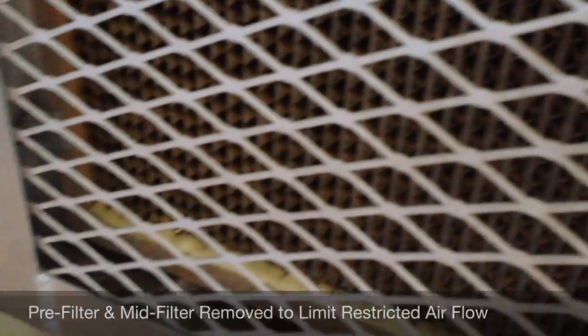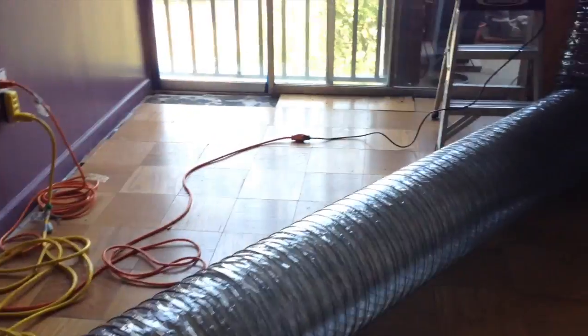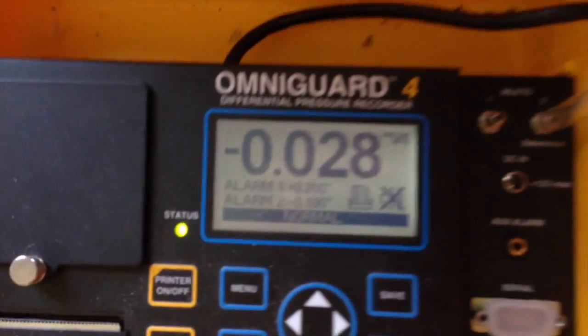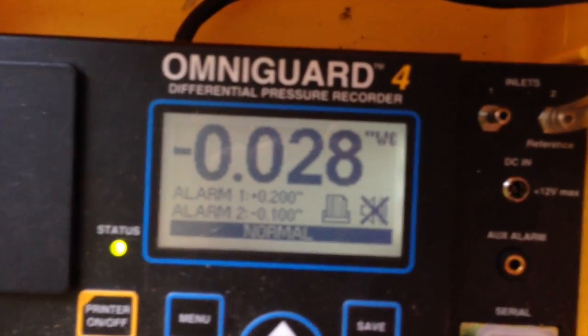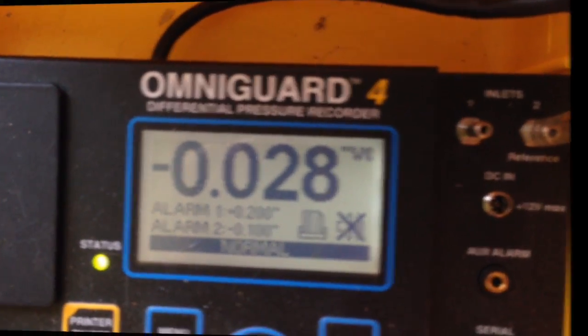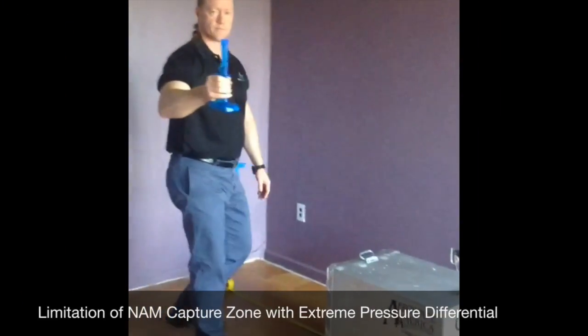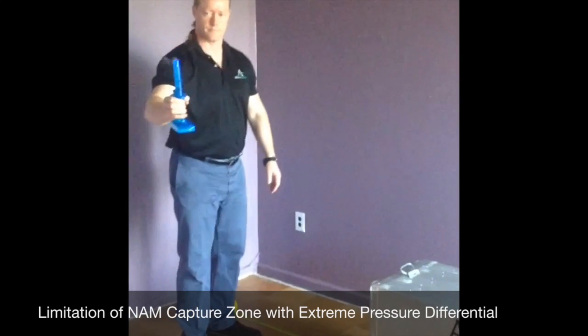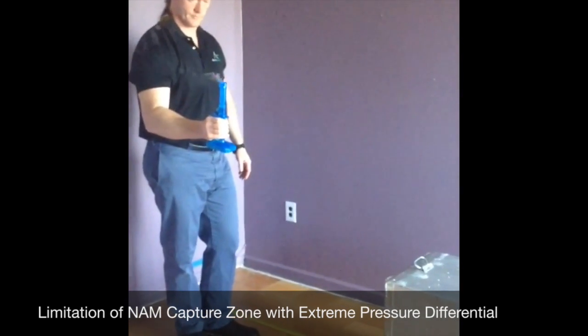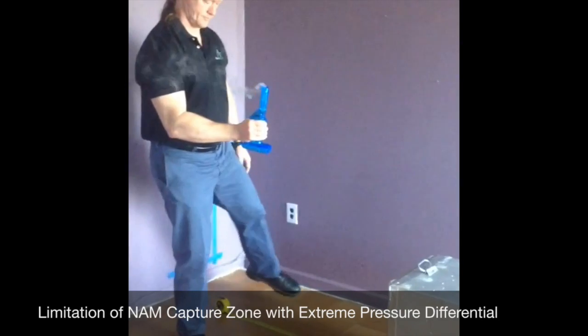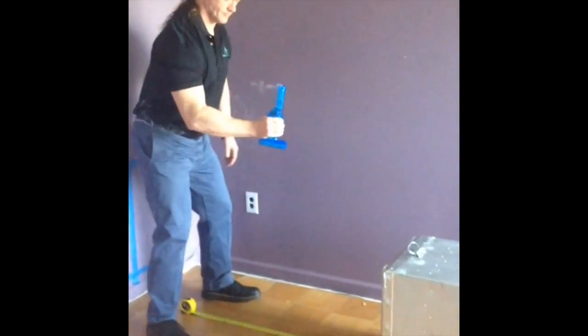This shows a negative air pressure differential containment recorded in excess of 0.02 inches of water column, as recommended for asbestos abatement and mold remediation. It only cleans a small parcel of the containment. Many believe the pressure differential creates a vacuum, expanding the capture zone of the negative air machine farther than the use of HEPA filtered air scrubbers.